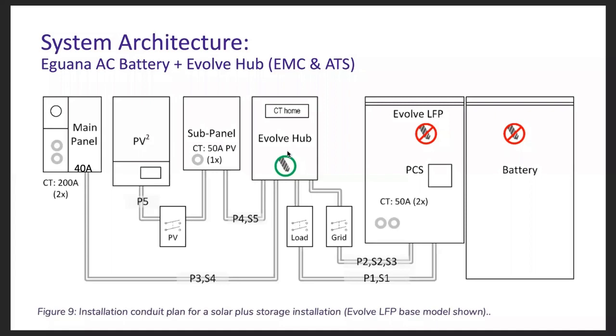It's UL 1741, and this is a good point to note: one of the best value-add features of that Evolve hub is, for example, in a situation where you've got a service panel with a 200 amp main and you've got a PV already installed, 7,600 watts, with a maximum 40 amp backfeed circuit going into that service panel. If you want to add another grid side inverter, per the interconnection rules of the NEC, you would have to either derate the main in order to add more backfed breakers to the same 200 amp panel, or upgrade the service.